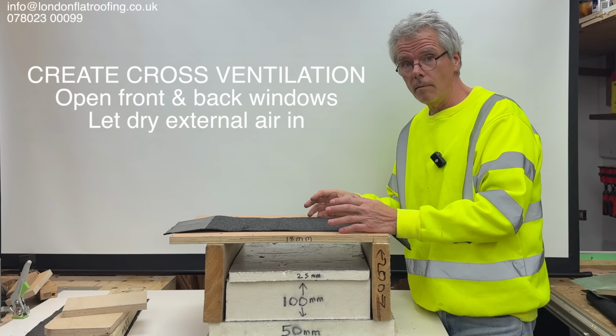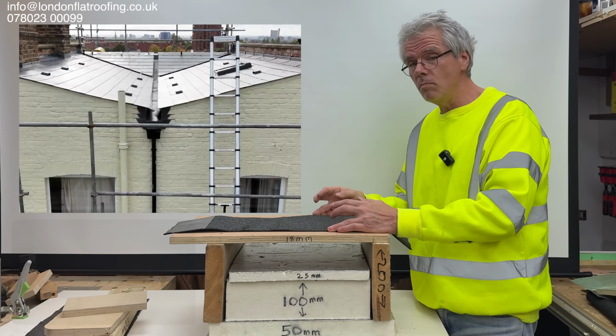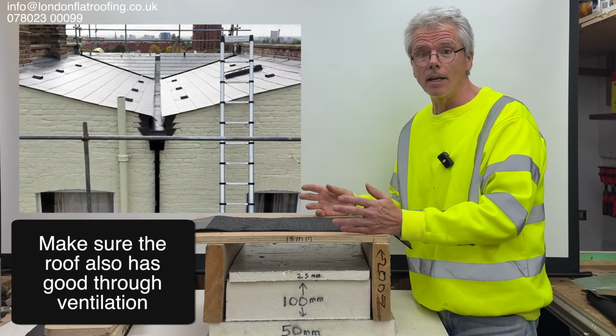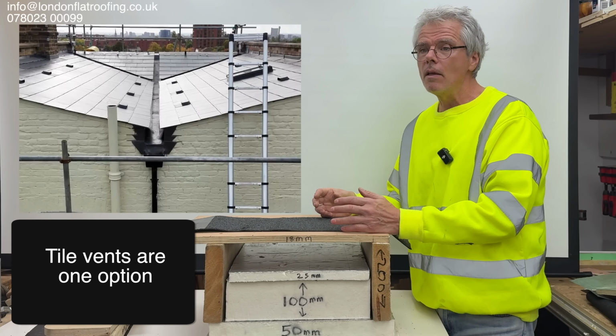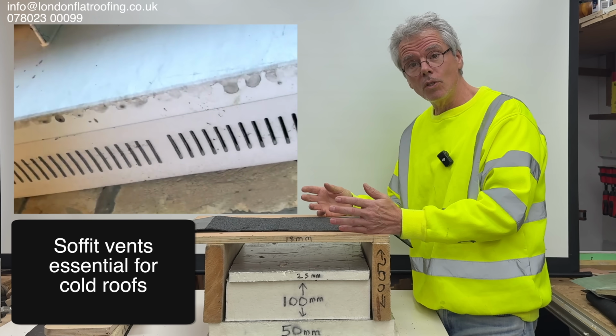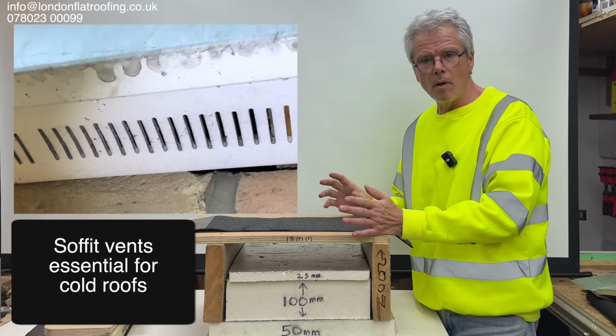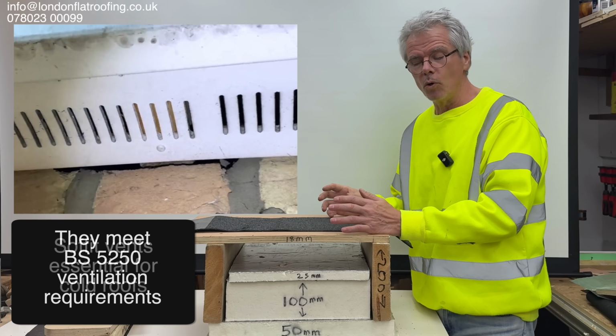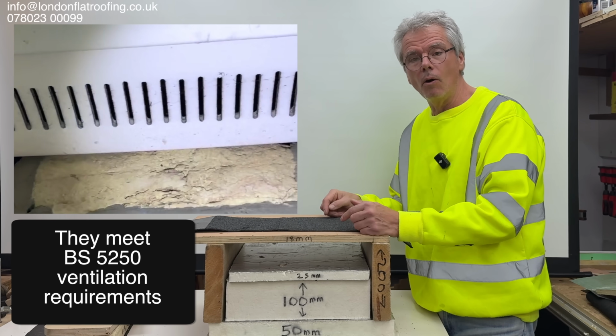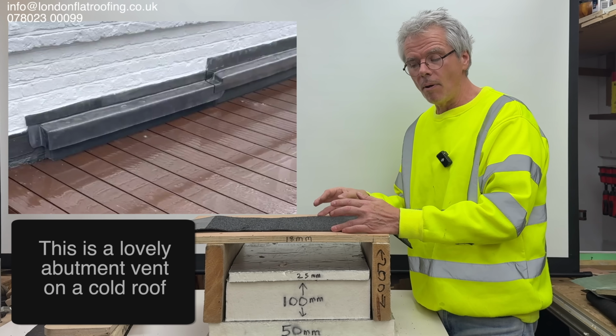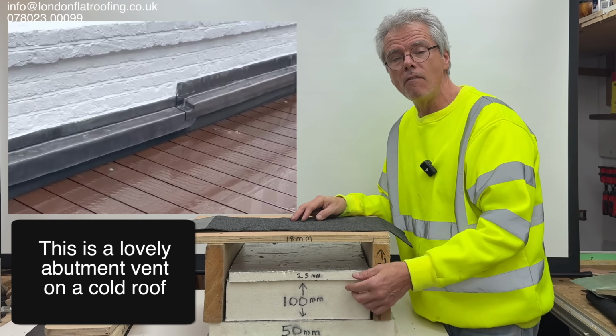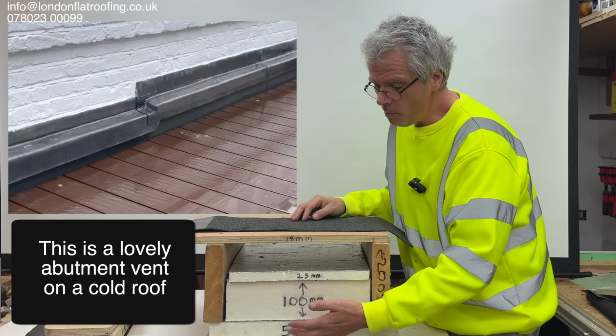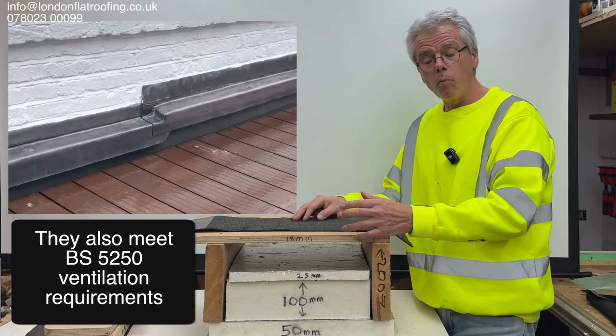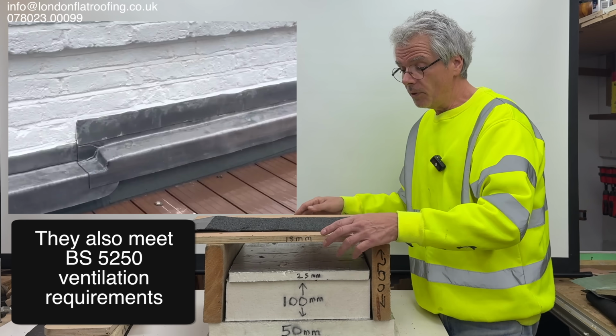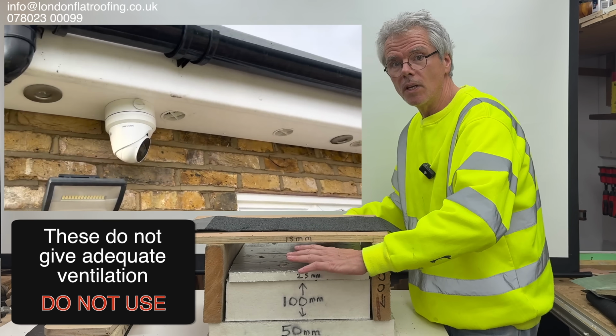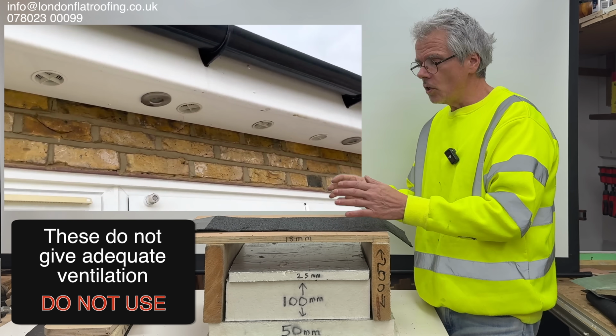Now, assuming that the parameters are the same, and assuming that outside is what we would call a drying day. If outside is raining and wet, you might be bringing in a little bit more moisture than you're taking out. But these are all to do with good, sensible management of internal moisture down below in the rooms. That moisture in the rooms down below is not going to apply pressure to your air vapor control layers. It's going to help stop that moisture getting up from in here, but whatever moisture has got up in here is going to be less, and the through movement here is going to help dry out the roof. So just think about it.